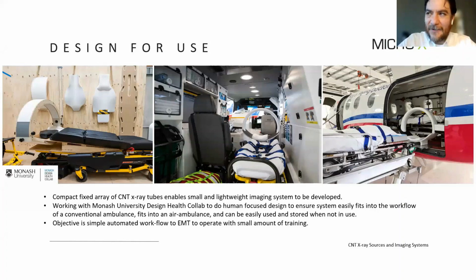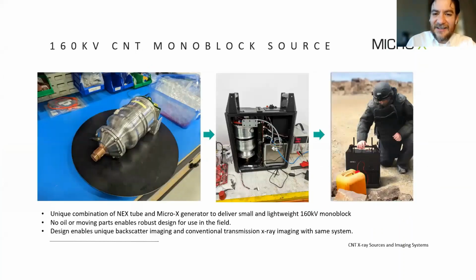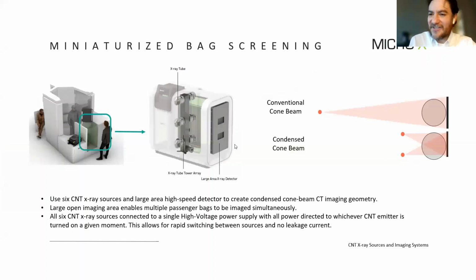You are right that it is the passenger taking responsibility in the airport scenario, but it is still a very controlled scenario. In that one, the system is actually a completely enclosed lead box. So when the passenger hits it, there's no radiation coming out of it for them to be exposed, and they have no way of getting into it when it locks. But you are right, we are broadening it. The way that we do that is by ensuring that the system can only take specific exposures in specific settings to provide that protection.